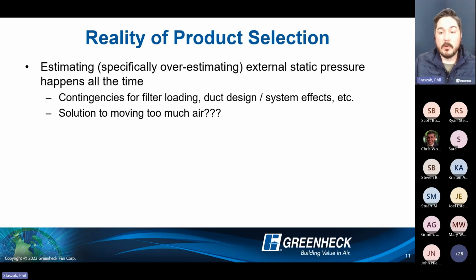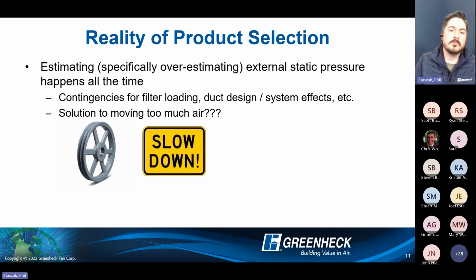And this is the reality of most product selection, unfortunately. Again, many jobs come across my desk laid out at a 1/2 inch and a 1/4. We're victims of always overestimating or compensating for static. And if it's not there, that system's going to move too much air. And the only solution to that is slowing these fans down.